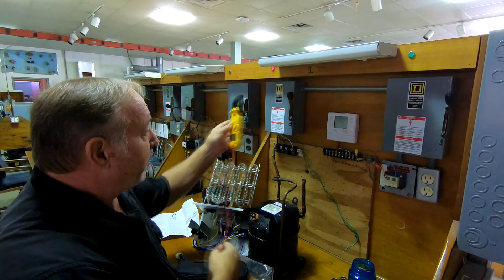The one important thing: no rings, no watches, no necklaces. The wedding ring goes in my pocket. Now I'm going to take a voltage reading across L1 and L2, and as you can see, I'm showing 209 volts. If I go between L1 and L3, I still have 209 volts, 209.3.